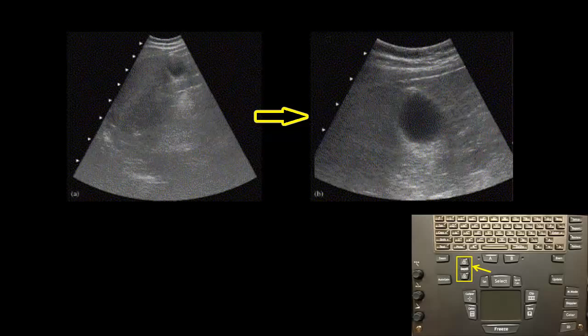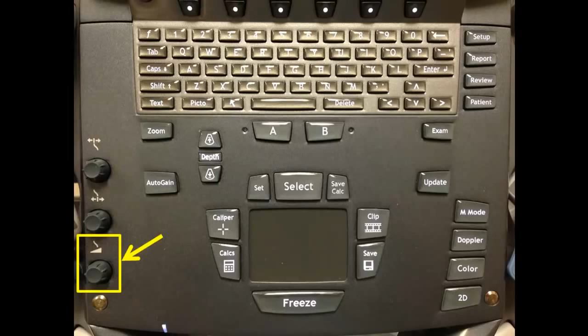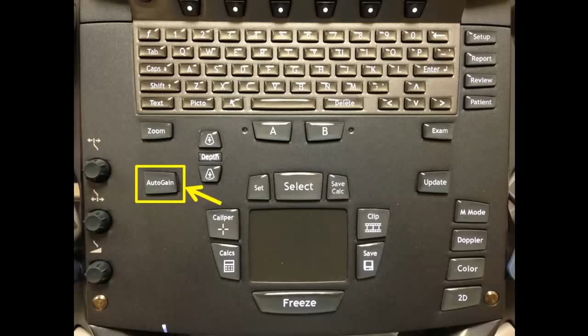Another helpful feature is gain adjustment, which fine-tunes the brightness of reflections on the screen. Near-field gain selectively adjusts the brightness of objects at the top of the screen. Far-field gain selectively adjusts the bottom of the screen, and overall gain adjusts the brightness of the entire screen. Lastly, if you're really struggling to get a decent picture, you can get a good start by using the auto gain button here.